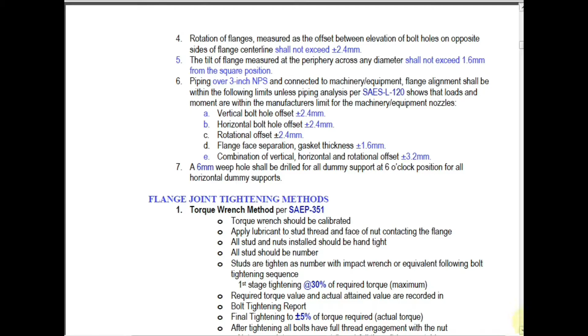2. Bolt tensioning method. Hydratight 50% tensioning method. Pressure gauges in the tensioning machine are calibrated. Mark bolts in 2 sets, Set A and Set B. Tensioners are fitted to every other bolt of Set A. Pressurize the tensioner to the predetermined pressure A per approved procedure. This is repeated 2 more times. Transfer the tensioner to Set B bolts, pressurize to predetermined pressure B and tighten nuts. This should be repeated 2 times. Note: pressure B is lower in value than pressure A.